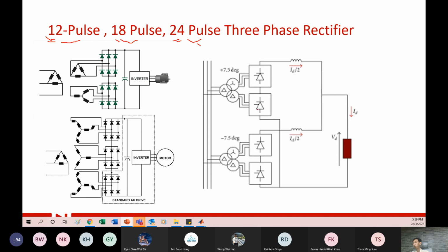Like I say, in the industry so far I see only up to 12 pulse. They don't go to 18, because in terms of cost and economy it's not feasible. You pay so much money and the harmonics come down just a little bit. So 6 and 12 pulse are most commonly used. 12 pulse is commonly used in train systems. The DC train systems use 12 pulse, not 6 pulse, because the 6 pulse harmonic is much higher.